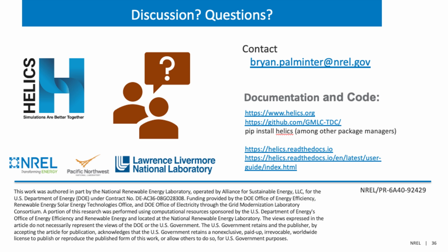And then I mentioned on the cybersecurity side before I got cut off, there's a real potential there too, with denial of service attacks, where malicious actors are intentionally flooding whatever network connection we have with so much traffic that it causes a bottleneck and can slow things down. Those types of delays can become very real, and we've definitely seen them in some places in the field already too. So capturing those delays can become quite important across a number of different timescales when we start to think about DERs, and can also help us design the right control architecture that makes sense, and the communication architecture behind that control architecture.